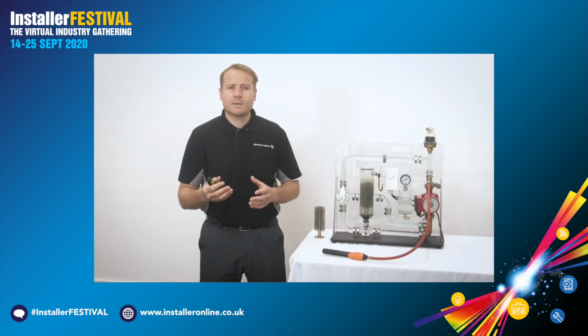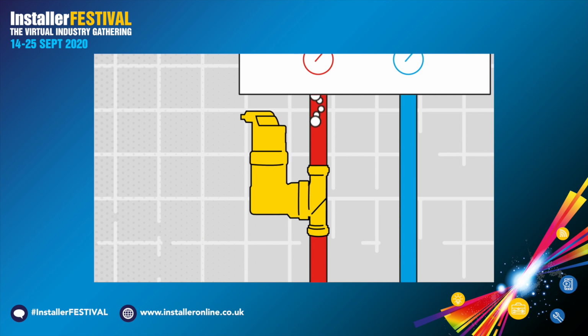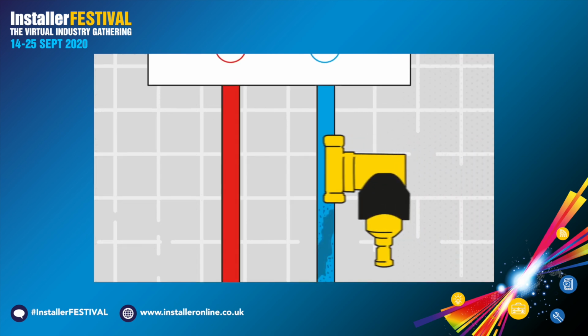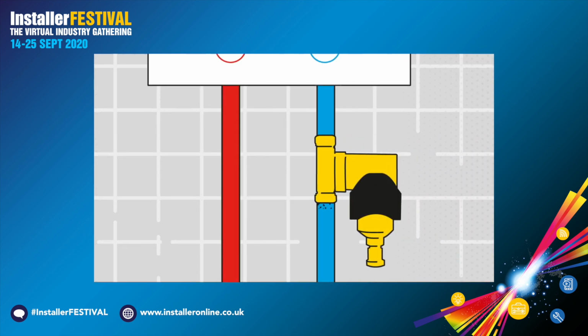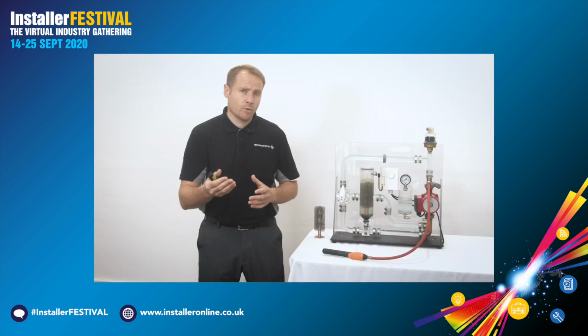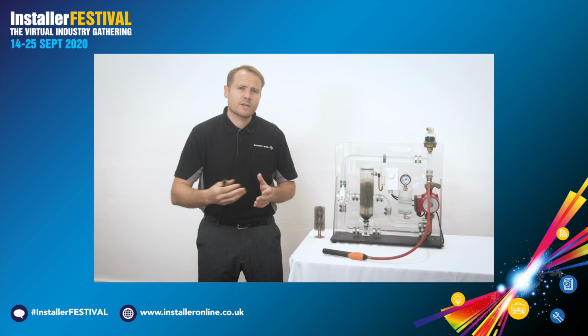Deaeration is based on high temperature, low pressure. And so for the inline units, these are generally fitted on the flow pipe coming out of the boiler. For dirt separation, these are generally fitted on the return pipework to the boiler to protect the most expensive component, the boiler, and of course any components thereafter.